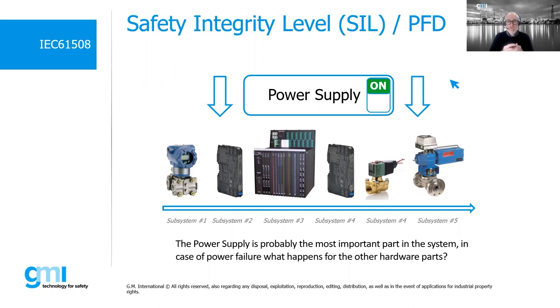And again, power interfaces, such as a safety relay, which will then act on a valve and on an actuator, which allow us to bring the system to safety in case of need. The main concept that needs to be understood is that every single element of a SIS must be sized with a SIL level, such as to allow us to obtain the overall SIL of the SIS required.